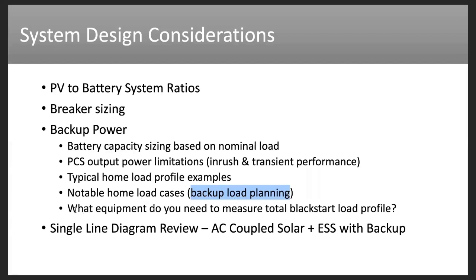And if you are going to be, and you should be planning that backup loads panel, what type of equipment would you need to measure total black start load profile? So your backup loads panel, all of the loads that you plan on putting on there, you should measure them to know what the inrush characteristics are, what types of loads they are, and what potential effect they may have on the voltage waveform.